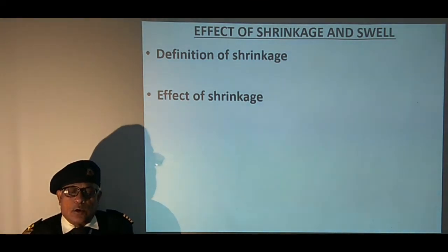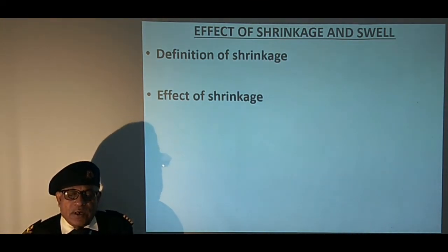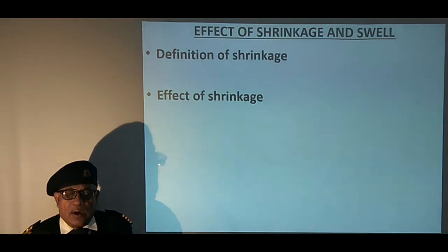If water level is controlled on the basis of indicated water level, then the controller will increase the quantity of feed water being supplied to the boiler, resulting in high water level when load stabilizes.